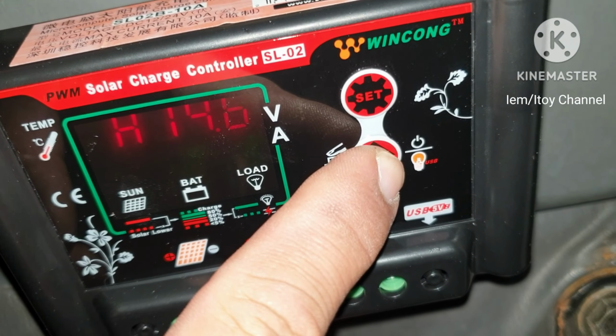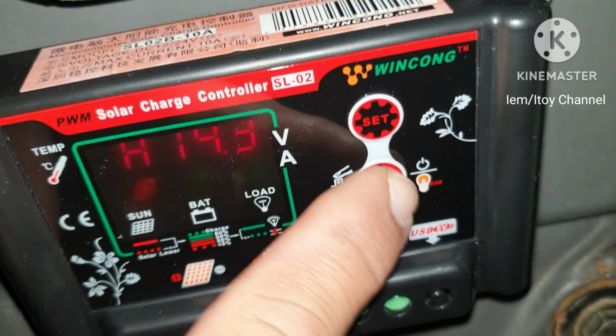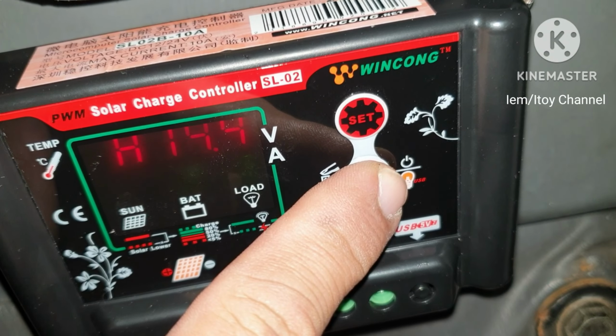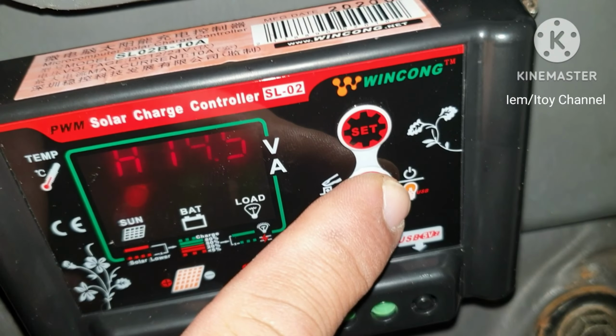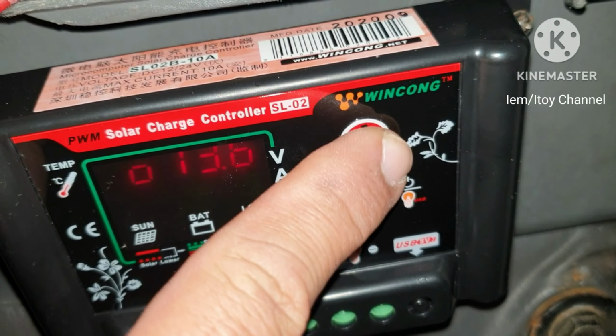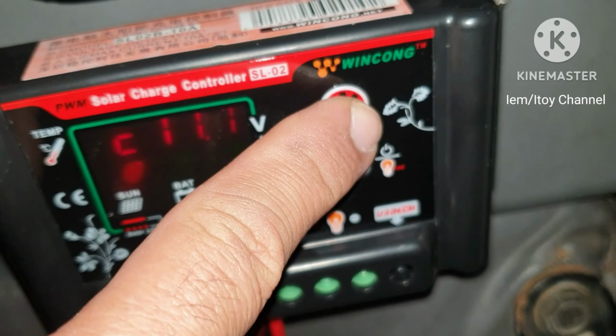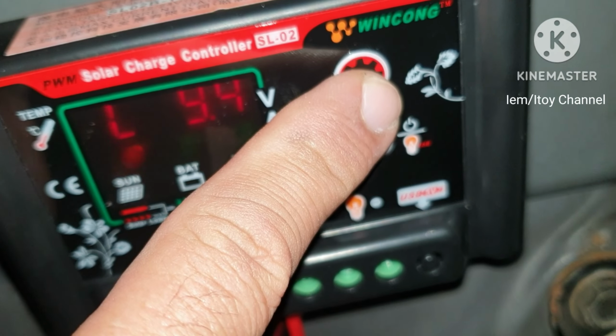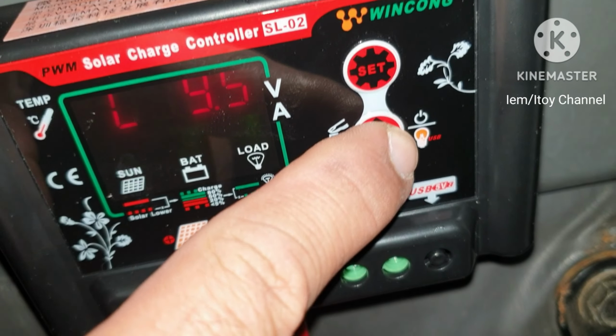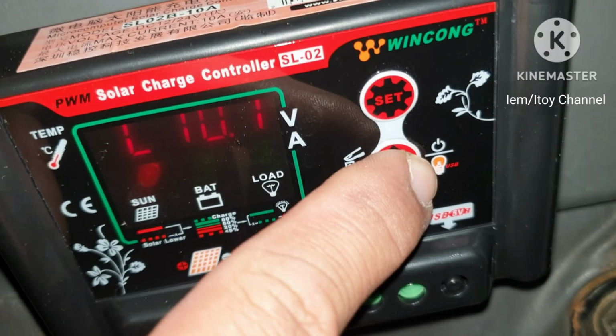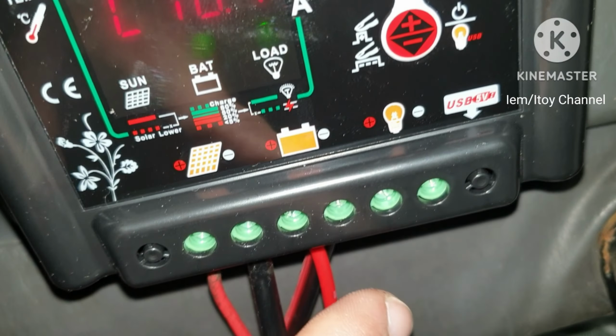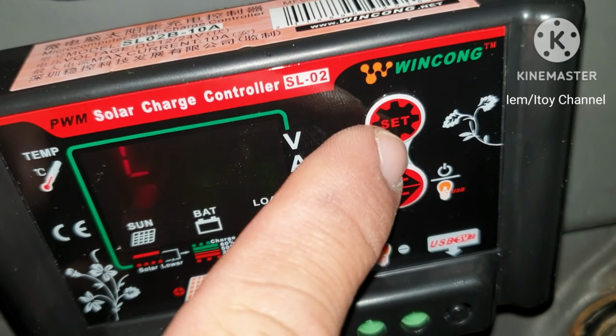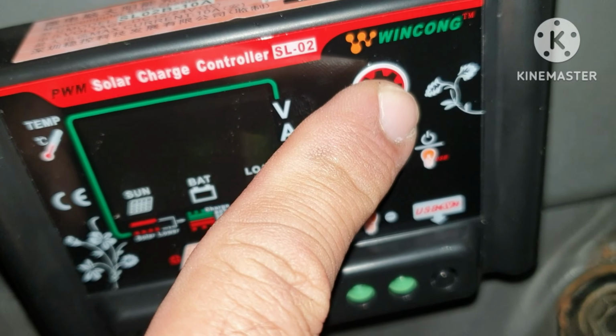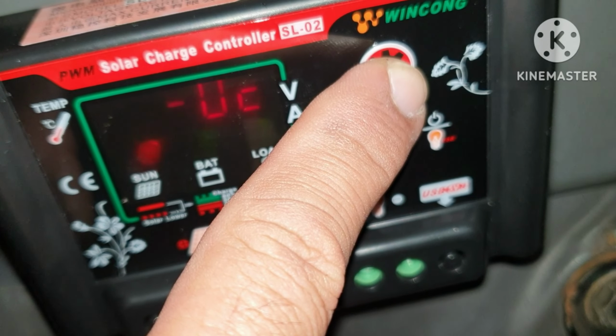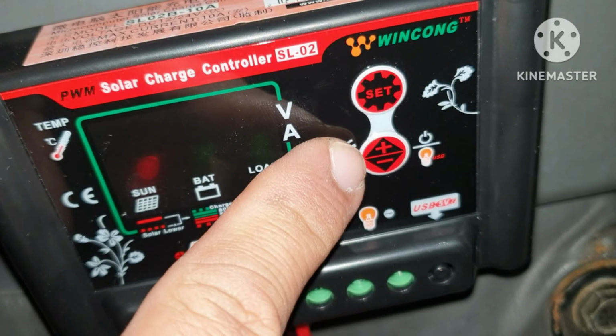Press and hold to decrease to desired settings, or press again to increase. Then press the top button for the float voltage setting. Next is the low voltage return setting, then the low battery voltage setting to disconnect the load. Lifepo4 should not go below 10 volts. This will disconnect the load connected here. Last is the battery temperature setting.